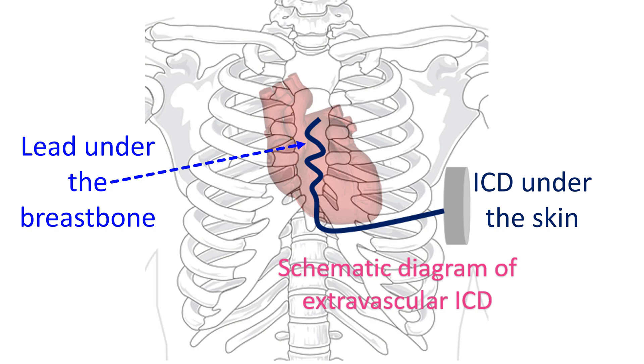The novel concept of extravascular ICD is to counter the shortcomings of transvenous ICDs and subcutaneous ICDs. In extravascular ICD, the lead is implanted under the breast bone over the heart. This avoids the presence of bone between the lead and the heart, improving the electrical performance of the device. Extravascular ICD can suppress fast heart rhythms by overdrive pacing as well as give successful shocks at lower energies comparable to transvenous ICDs.